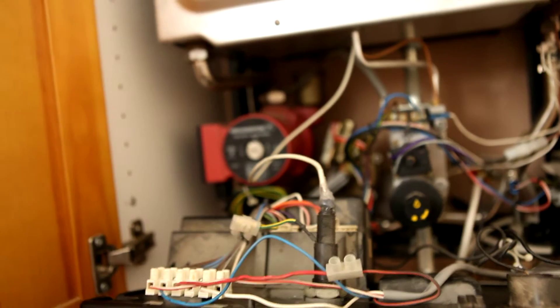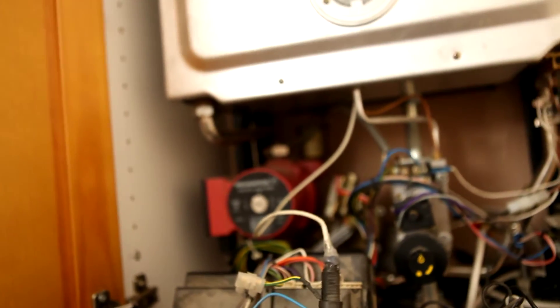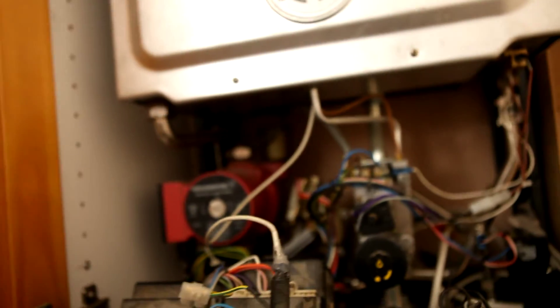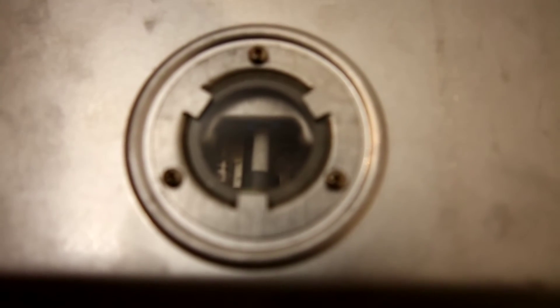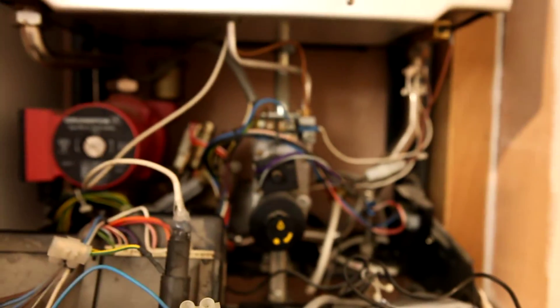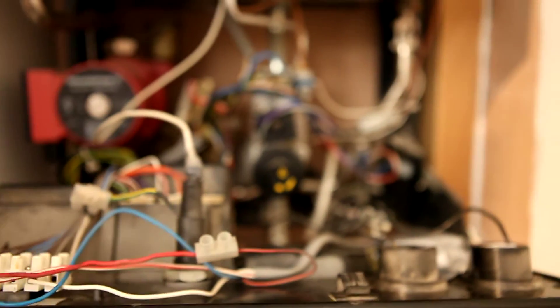So we fire it up with the water, boiler flames, massive flames come up in through the boiler burner window, the water's not actually running at the moment, massive flames come on, massive flames stay on, water gets absolutely scalding hot, sounds like the boiler's about to explode from boiling water, flames still stay massive, and then they go out when the boiler trips on the overheat stat.